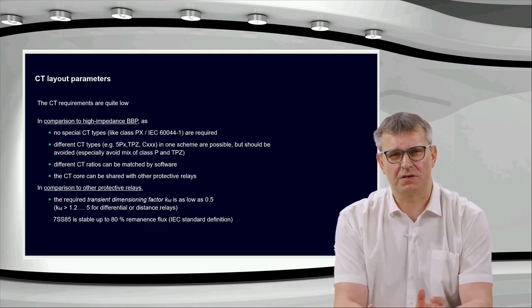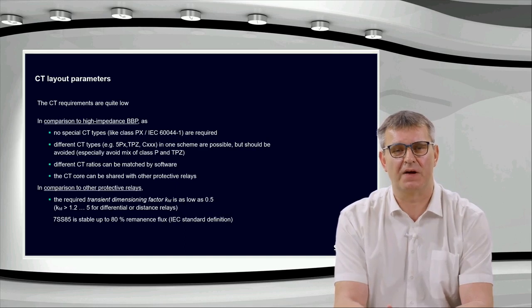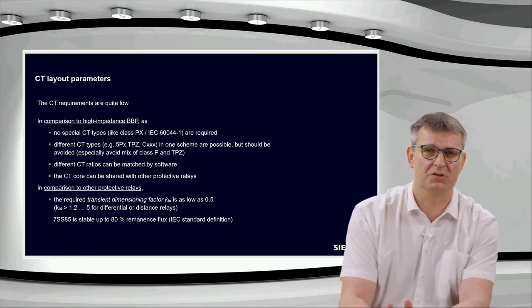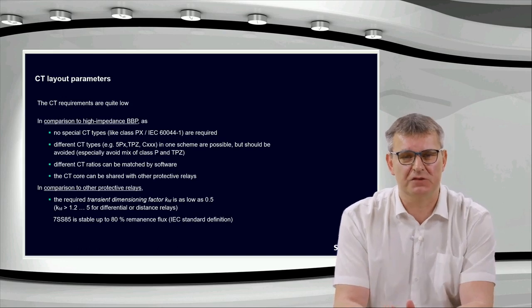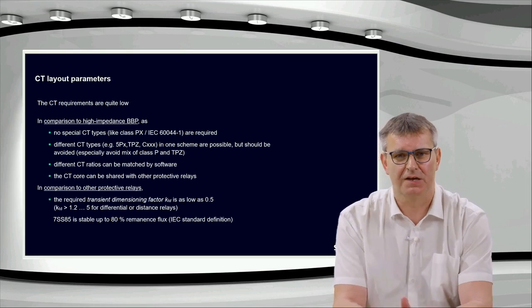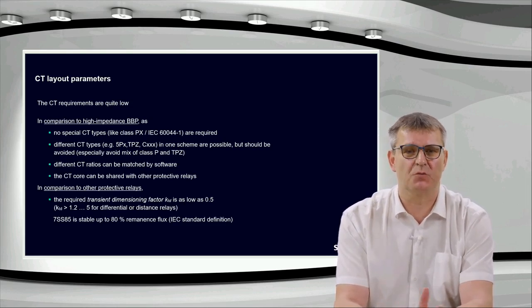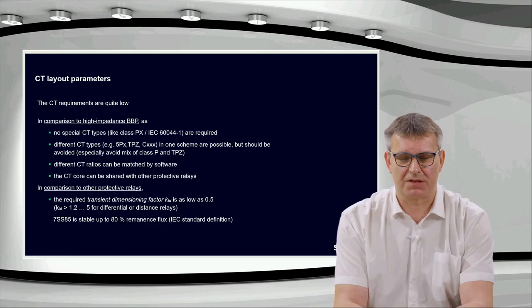What is for sure, if somebody says, okay, the CT has been dimensioned to fulfill the requirements for distance protection, to fulfill the requirements for transformer protection, then no further calculation is necessary. You can immediately say, okay, it's fine for distance protection. No questions. We can use the core also for the busbar protection device. This sometimes astonishes a little bit.